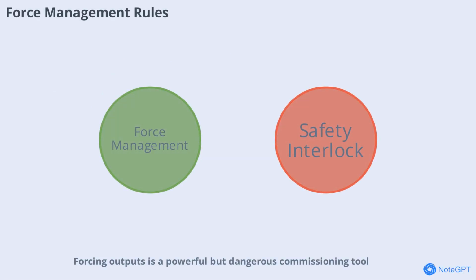Forcing outputs is a powerful but dangerous commissioning tool. The guide establishes a critical rule. At the end of every day, you must check the force list in CBM and remove all active forces. Forgotten forces, especially on safety interlocks, can cause severe accidents. Proper force management is essential for maintaining system integrity and preventing unintended operations. Let's understand the importance of this rule and how it safeguards the commissioning process.